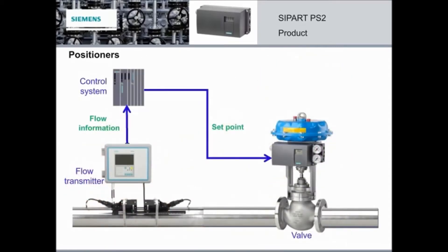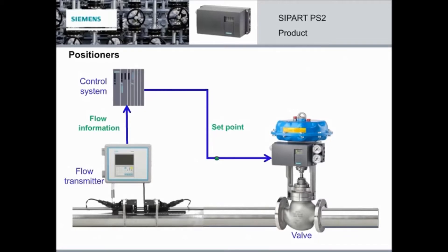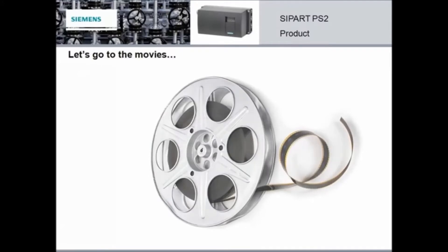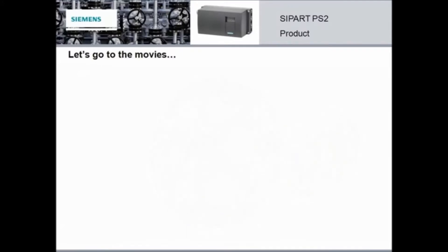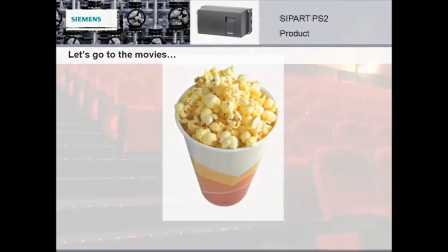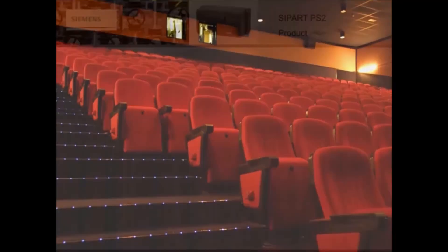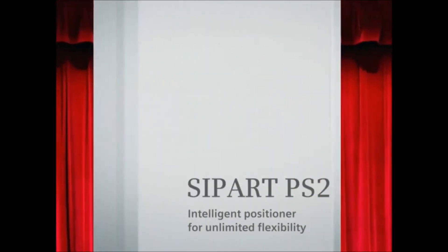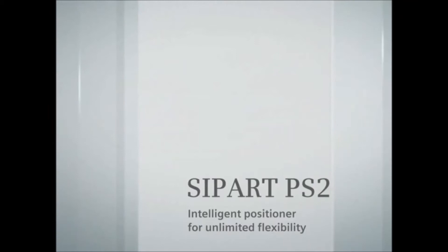And here's how it works. The positioner receives the set point, detects the valve position, and then changes the compressed air supply of the actuator in order to drive the valve to the requested set point. Now that you have a better understanding of what a positioner is and what it does, it's time for the big event. So grab your popcorn, pick a seat, and get ready for this blockbuster hit starring the one and only SIPART PS2.